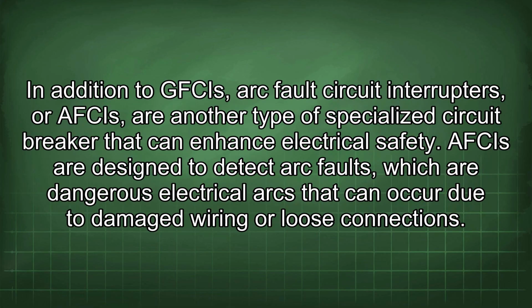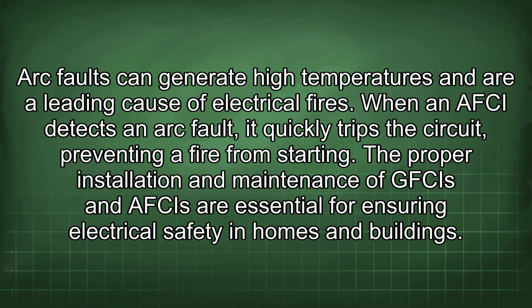In addition to GFCIs, arc fault circuit interrupters, or AFCIs, are another type of specialized circuit breaker that can enhance electrical safety. AFCIs are designed to detect arc faults, which are dangerous electrical arcs that can occur due to damaged wiring or loose connections. Arc faults can generate high temperatures and are a leading cause of electrical fires. When an AFCI detects an arc fault, it quickly trips the circuit, preventing a fire from starting.